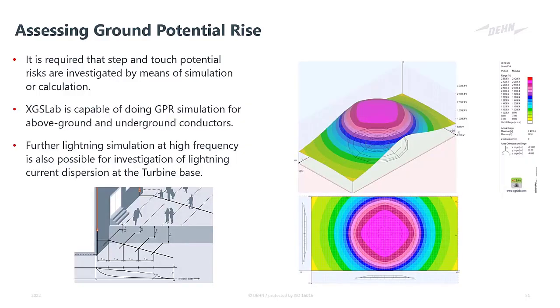Now, it is a requirement to make sure that the earthing system is safe against step and touch during electrical faults, because this is also seen as a small substation. There are transformers located inside the base of the wind turbine, and in this case we did a step and touch calculation using XGS Lab software. We used the XGS FD or frequency domain model, and with that we can do both above ground and underground conductors. Now you can see here that we control the step and touch or the ground potential rise very nicely in the center portion, so there are not very big differences.